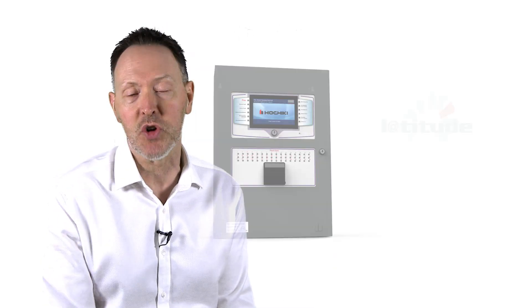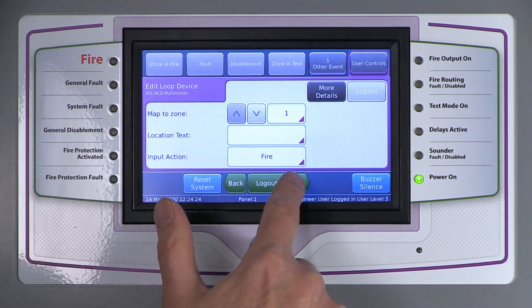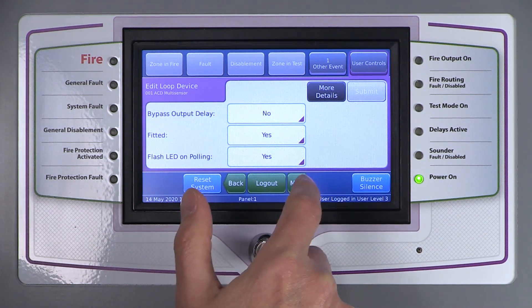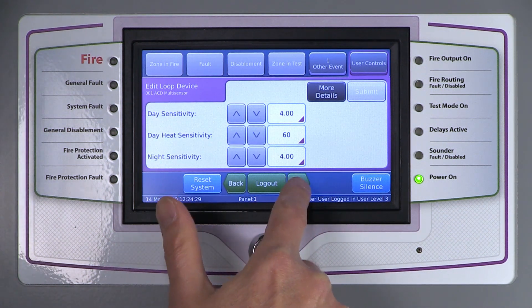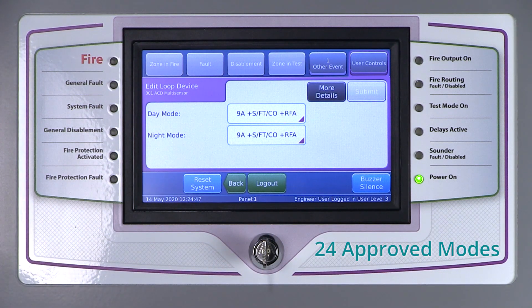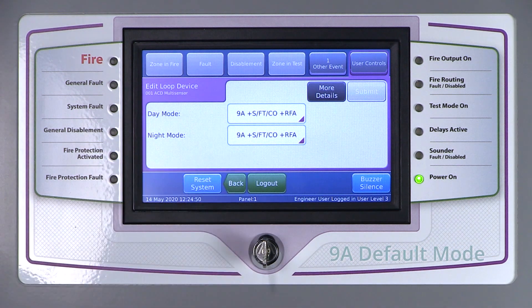Let's take a look at the sensor on our working loop. For the purposes of this video, we are showing the ACD on Hochiki's own control panel, the Latitude. Here's the Latitude's touch screen, and we already have located the ACD on loop number one. Remember, we have 24 modes to choose from. This ACD is currently set at mode 9A, which is actually the default mode. So out of the box, every ACD operates on this mode.